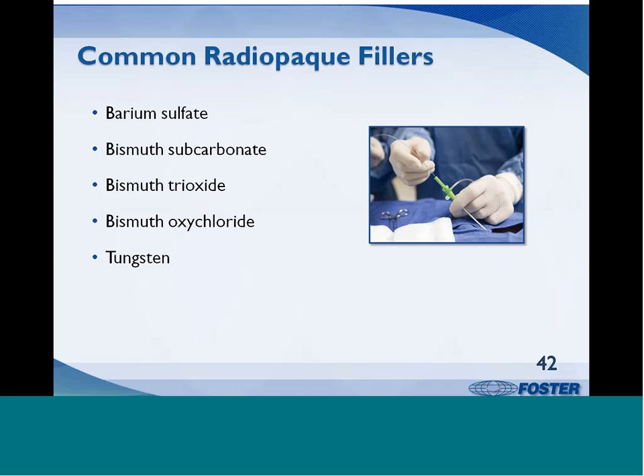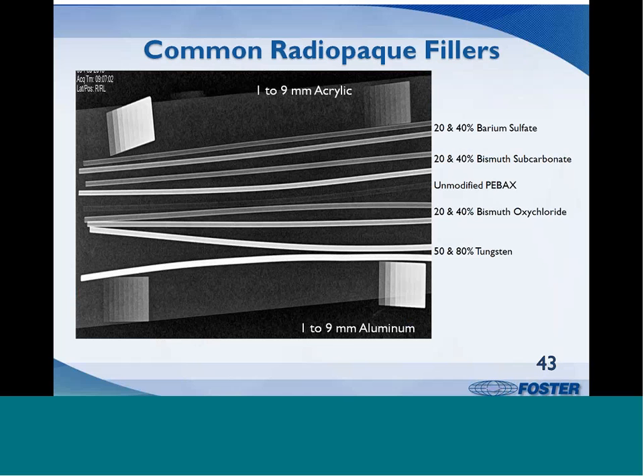The key fillers are barium, bismuth, and tungsten-based. This X-ray shows the effect of loading on the different types of radiopaque fillers. Starting from the top, you can see 20 and 40% barium sulfate and 20 and 40% bismuth subcarbonate. The middle tube that you can barely see is the unmodified neat resin. Continuing with 20 and 40% bismuth oxychloride and 50 and 80% tungsten. The corner blocks are aluminum and acrylic step blocks to help gauge the effectiveness of the fillers.